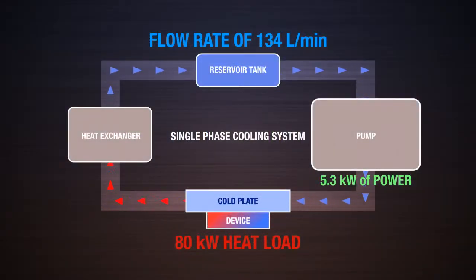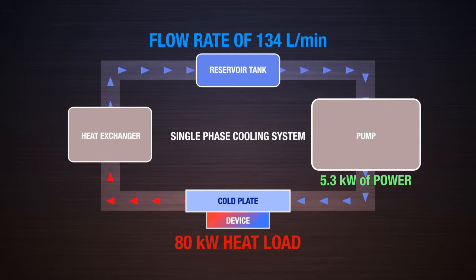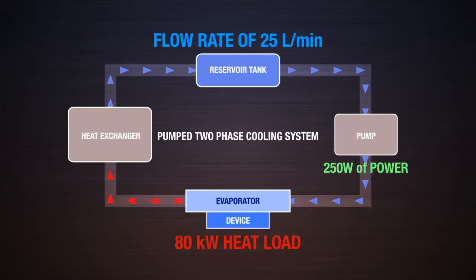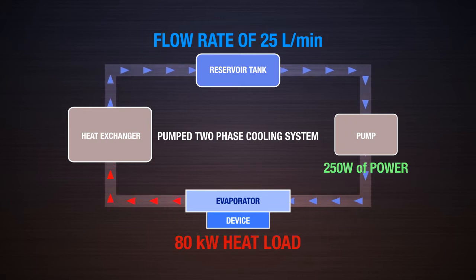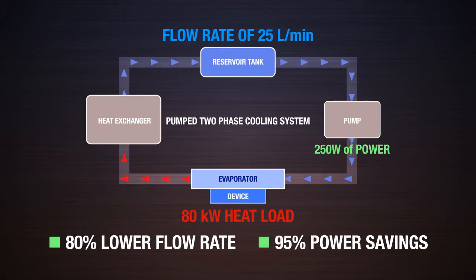This is important for applications that must be compact and operate with minimal power. In terms of weight and power savings, we've shown that for an 80 kilowatt heat load, a pumped liquid system would require a pump that utilizes 5.3 kilowatts of power and a flow rate of 134 liters per minute to remove the waste heat. By contrast, a pumped two-phase system would require pumping power of only 250 watts with a flow rate of 25 liters per minute — an 80% reduction in flow rate and a 95% reduction in power.